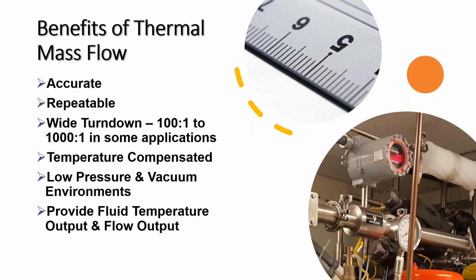And then the last one of the other benefits here to thermal mass flow is that we can provide basically a flow measurement output as well as a temperature output, because we've already got the sensors in place. You just need to tell us when we're going through the process of setting these units up and talking about your application, what you need to do. So you basically could be saving yourself some costs on buying a second unit because we can give you a temperature output that you could use in your process.